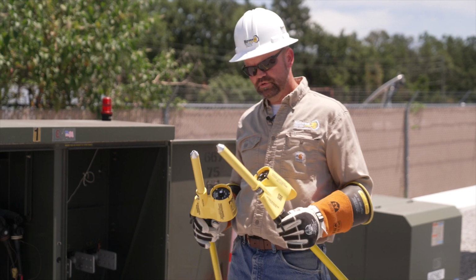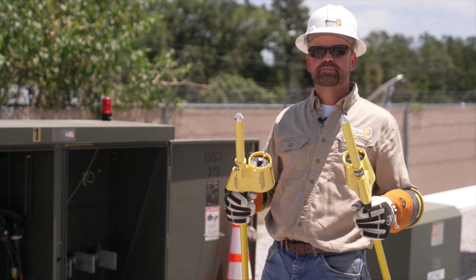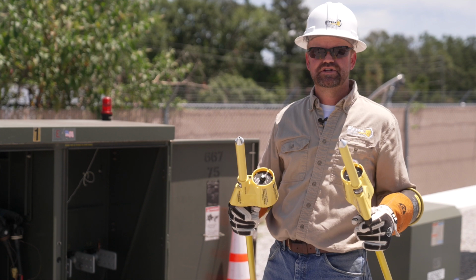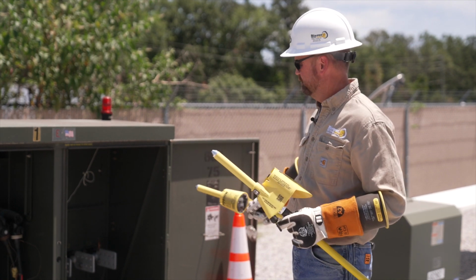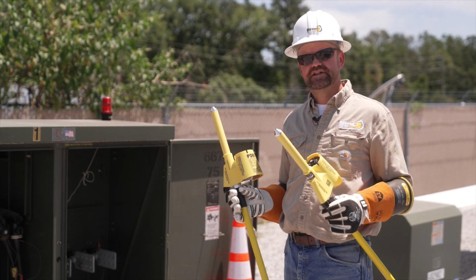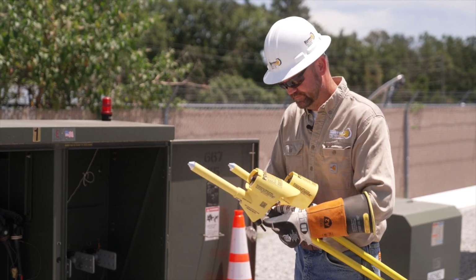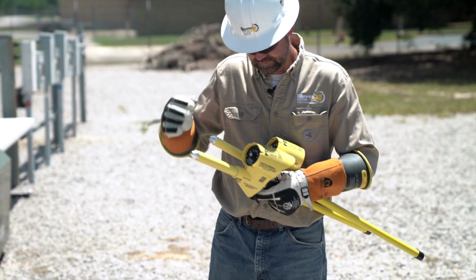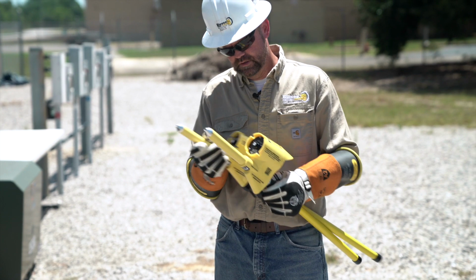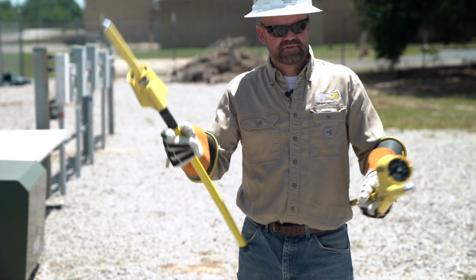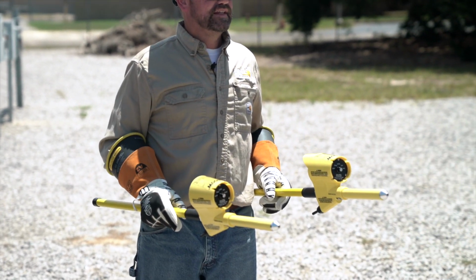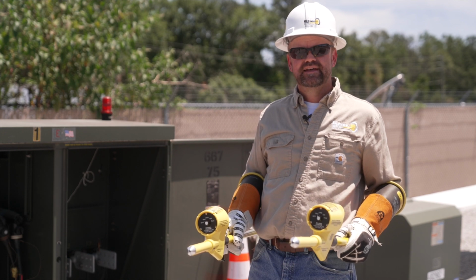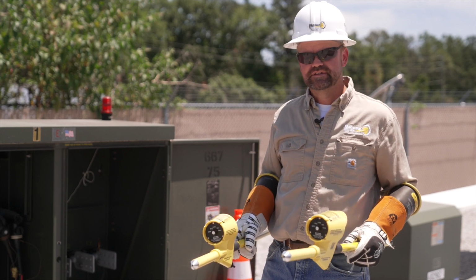So again, the first thing we'll do is put both meter probes in the DEG switch position, and we'll check our phase rotation on the secondary tabs, the 120/208. So both meter probes are in the DEG switch position, and now I'm ready to take my phase angle readings.